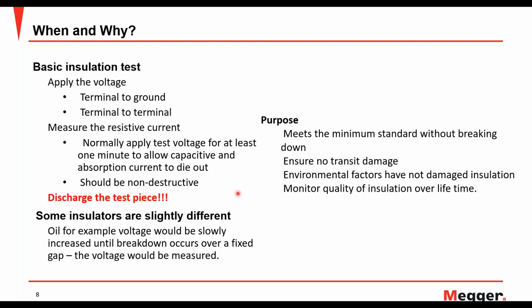And it should be non-destructive. Of course, you are not there to destroy your insulation, you are just there to test the integrity of the insulation. And at the very end, very important, discharge the test piece, basically ground it once you are done doing the testing.